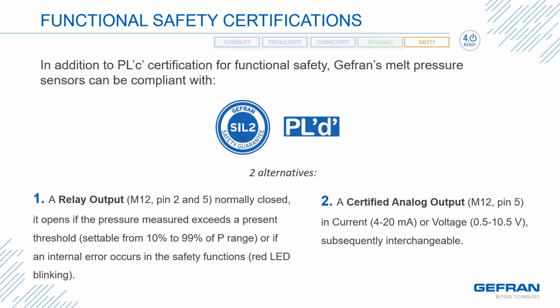In addition to the Performance Level C certification for functional safety, Gefran's IO-Link melt pressure sensors can be compliant with the safety guarantee level of SIL 2 and Performance Level D if chosen in the order code. There are two alternatives. A relay output, normally closed, that opens if the pressure exceeds a preset threshold. Of course, this threshold is easily adjusted via the IO-Link network, or if an internal error occurs in the safety functions, also indicated by a blinking red LED. The second is a certified analog output, either in current or voltage.